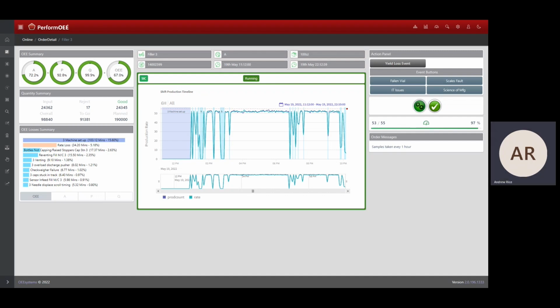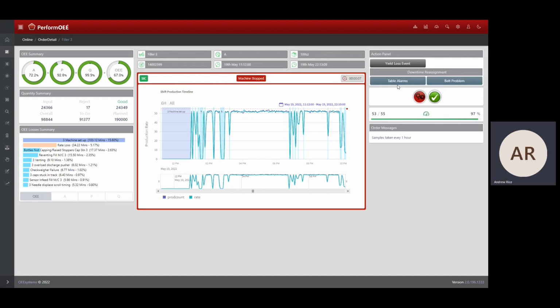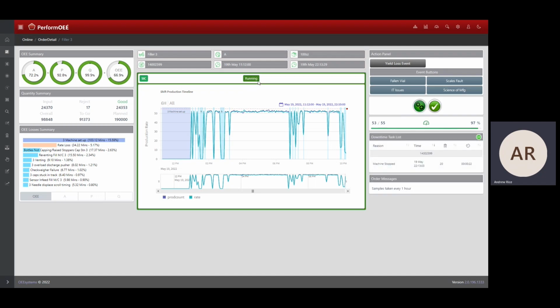If there is a machine, so that reason is marked as reassignable. If you get a reassignable reason coming into the system and the operator is trying to fix it and they don't get a chance to reassign it here with these quick restart buttons, by the way, you can have multiple restart buttons over here. If they haven't reassigned it by the time the line has restarted, so I'm just going to say, pretend that this is up to 18 minutes, for example, we're going to restart this line and the machine stop alarm is going to clear. What will happen is that alarm, because it was not reassigned, but it's been marked as reassignable, appears on the right hand side over here for reassignment. So there you can see we were down, say, for 20 minutes, and now we're asking the operator to reassign that downtime to what the true root cause was.